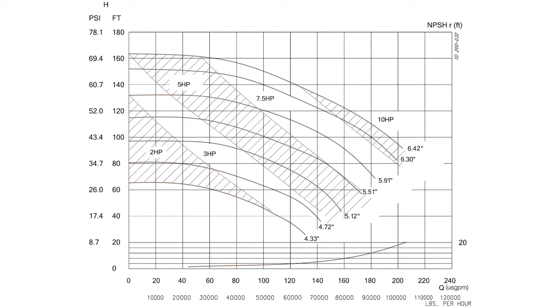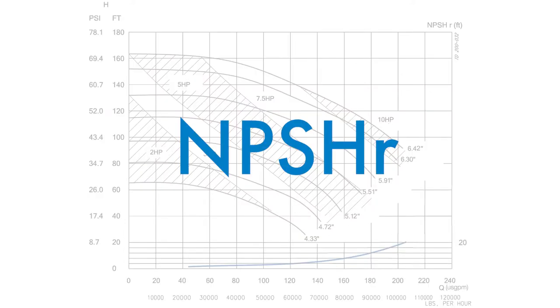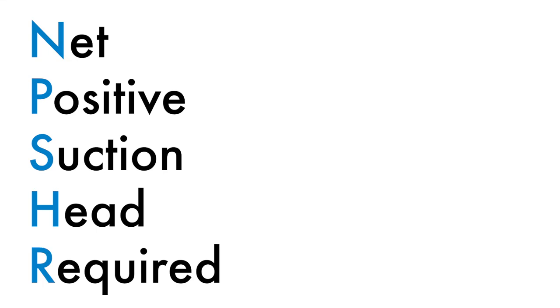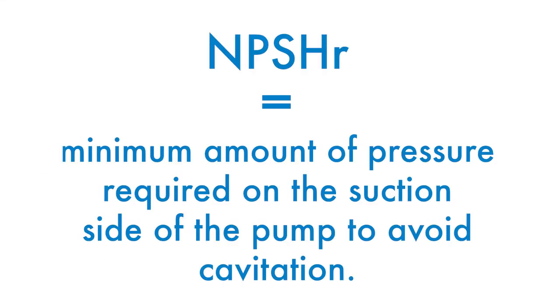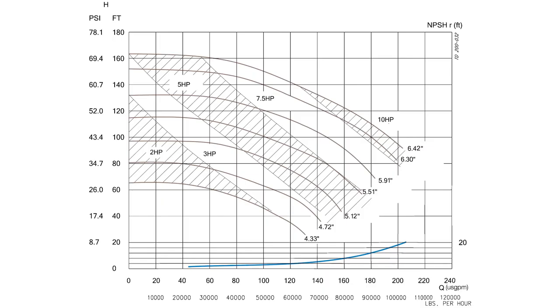In addition to standard PSI and flow, the curve at the bottom of the grid indicates NPSHR, which stands for Net Positive Suction Head Required. NPSHR is the minimum amount of pressure required on the suction side of the pump to avoid cavitation. NPSHR is determined by the pump, as each one is different.